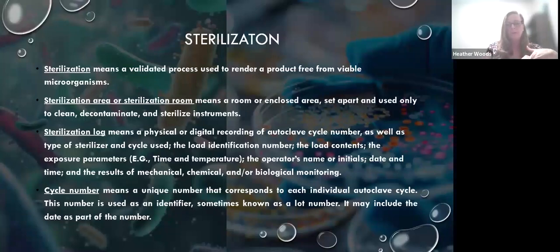And sterilization logs are important for us regulators. They're the physical or digital recording for the autoclave number, as well as a sterilizer, load number, contents, and they can also include the operator's name, initials, and time and date, and also the biological and chemical monitoring. And then also the cycle number, that's the identifier, sometimes known as a lot number, as Michael previously mentioned.